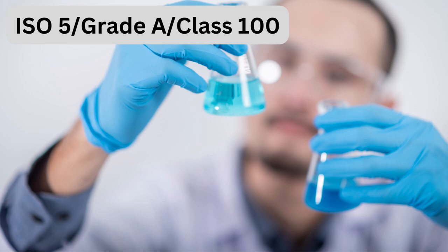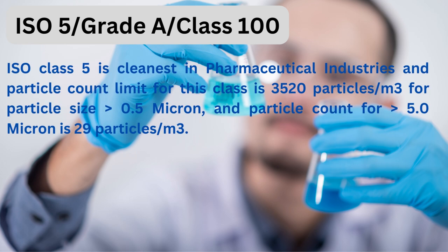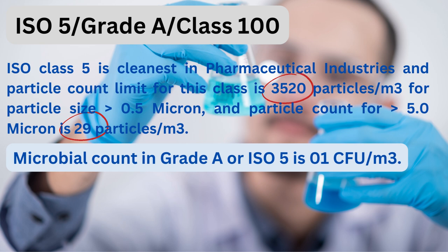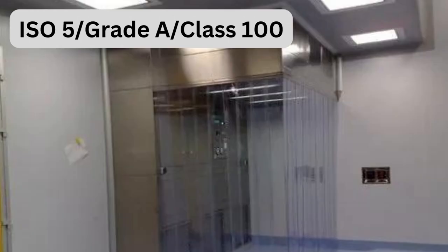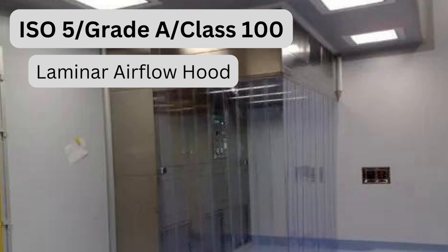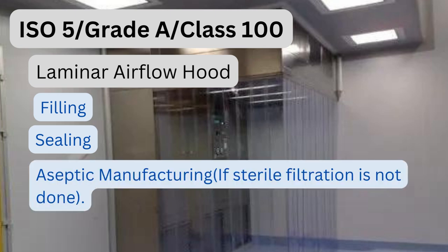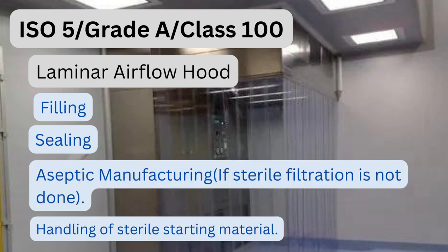ISO 5 corresponds to Grade A and Class 100. ISO class 5 is the cleanest in pharmaceutical industries. Particle count limit is 3,520 particles per cubic meter for particle size greater than 0.5 micron, and 29 particles per cubic meter for greater than 5.0 micron. Microbial count in Grade A or ISO 5 is 1 CFU per cubic meter. Air changes per hour are 240 to 480. Class A is achieved under laminar flow hood and critical operations take place here, for example: filling, sealing, aseptic manufacturing if sterile filtration is not done, and handling of sterile starting material.